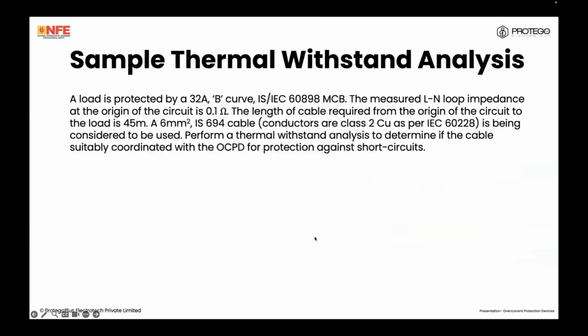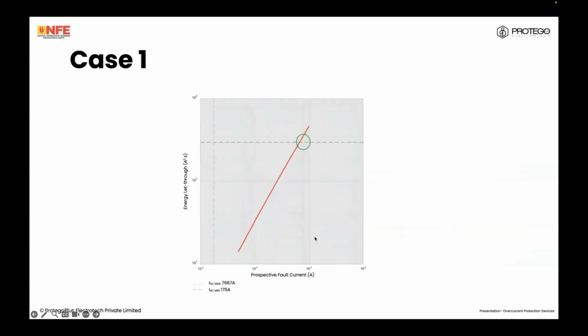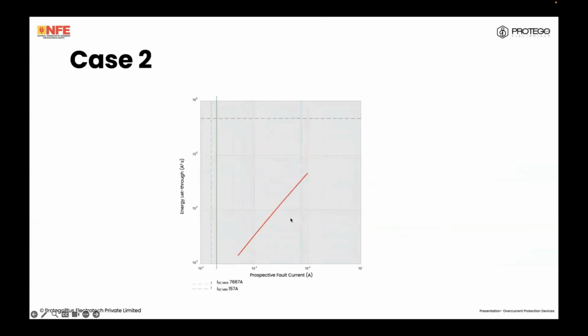So from a thermal withstand point of view, if your maximum earth fault loop impedance values are not satisfied, we are going to turn into case 2. Anyways, this was about that. I think we are running out of time. So protection against overload current I've presented many times at the NEC web events as well. So I will end the presentation here.